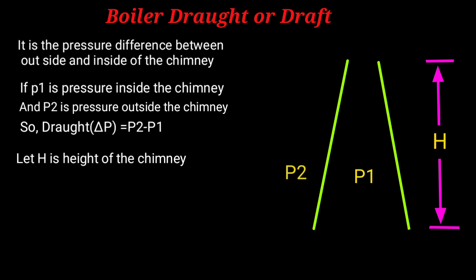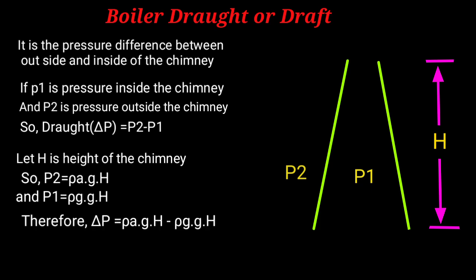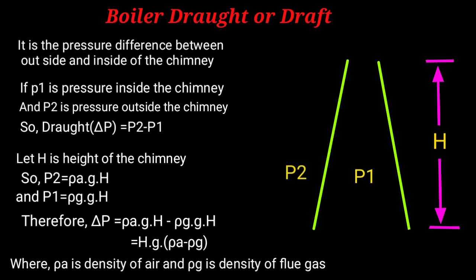Let H be the height of the chimney, so P2 equals ρa·g·H and P1 equals ρg·g·H. Therefore, ΔP equals ρa·g·H minus ρg·g·H equals H·g(ρa minus ρg), where ρa is density of air and ρg is density of flue gas.